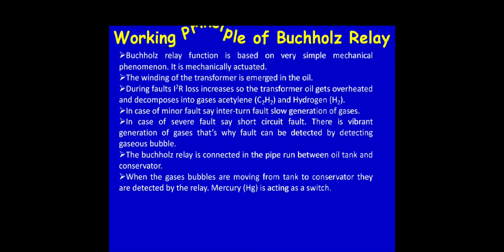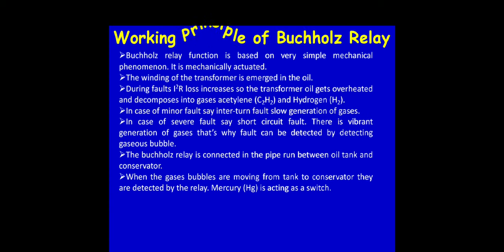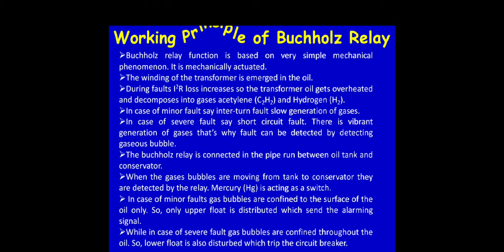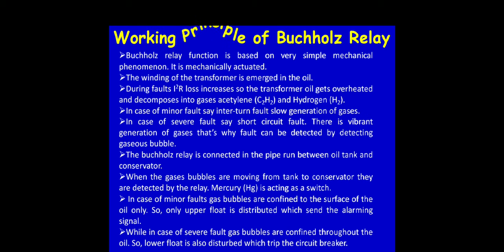The Buchholz relay is connected in the pipe running between the oil tank and the conservator. When gas bubbles move from the tank to the conservator, they are detected by the relay. Mercury acts as a switch. In case of minor faults, bubbles are confined to the surface of the oil only, so only the upper float is disturbed, which sends an alarm signal. In case of severe faults, gas bubbles are confined throughout the oil, so the lower float is also disturbed, which trips the circuit breaker.